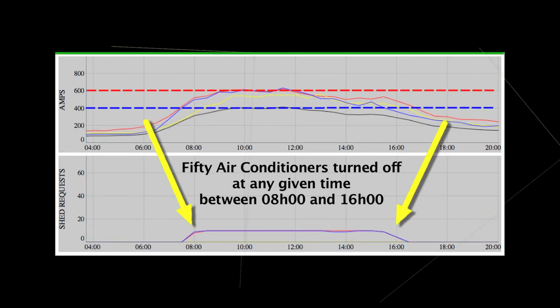But that's not all, as they say in the soapy commercials. Considering that 50 air conditioners were turned off at any given time between 8 o'clock and 4 o'clock, a considerable amount of kilowatt hours was also saved. Remember though, no air conditioner was turned off for more than 9 minutes at a time, and the switching cycles are also not less than 1.5 hours apart, which means that it's unlikely that anybody was aware of the intervention.